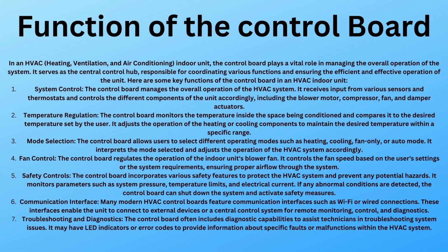And they are controlled by their own function board. When the downstairs system is satisfied, the upstairs thermostat that goes with your control dampers will actually close off the downstairs airflow and then increase the airflow to the upstairs. That increases cooling capacity to the upstairs, which will bring the temperature down in that room at a much faster rate. Basically, it's called a zone system.